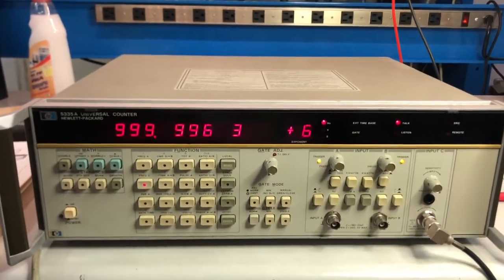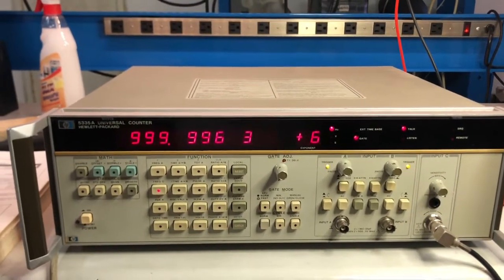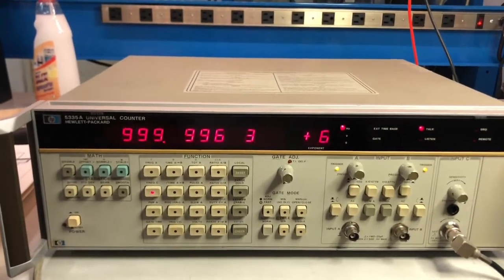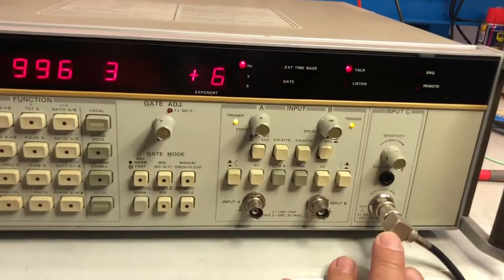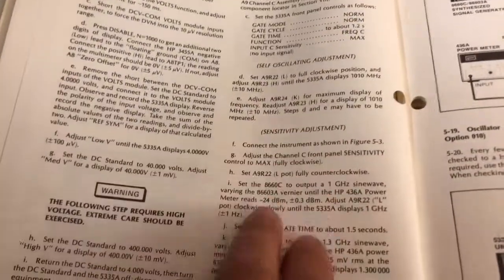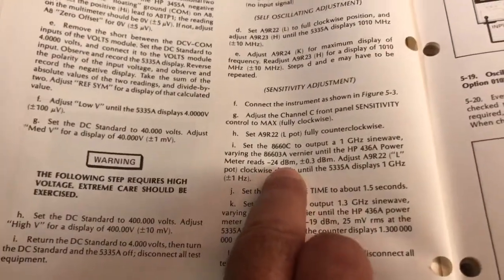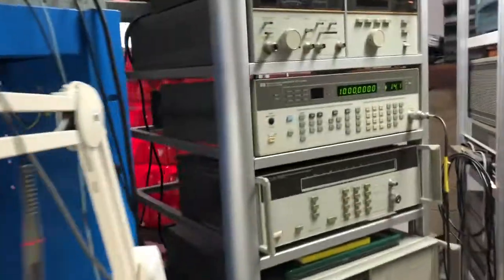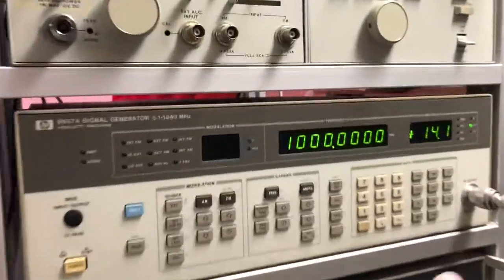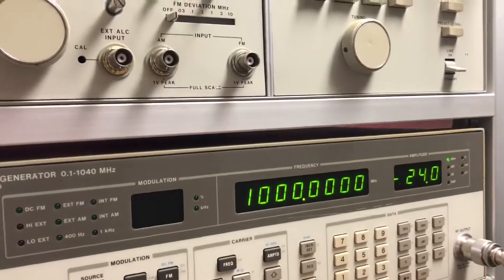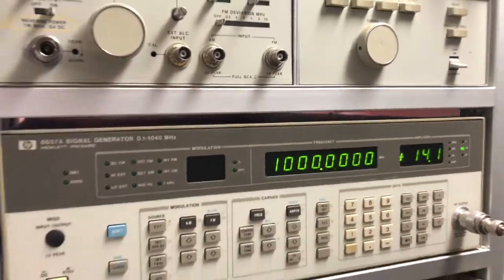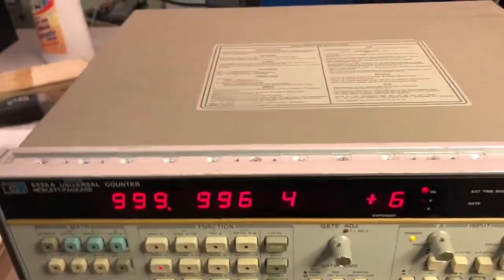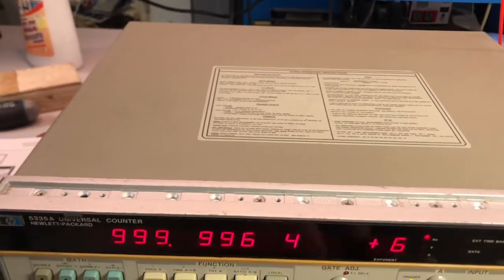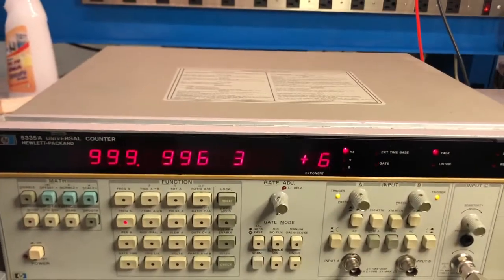The instrument reacts pretty fine, and it's very sensitive. It's required in channel C to be able to read down to minus 24 dBm, which is right now here, dBm minus 24, which means plus 14 millivolts, which is a very low level signal, and it's very stable. So I really like it. It's a very nice instrument.